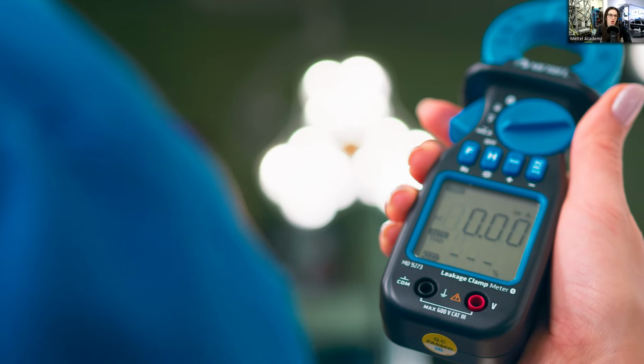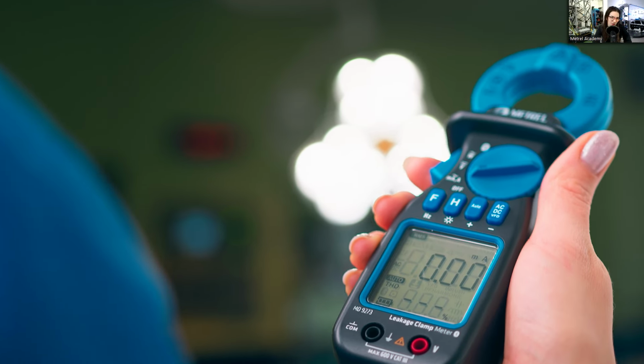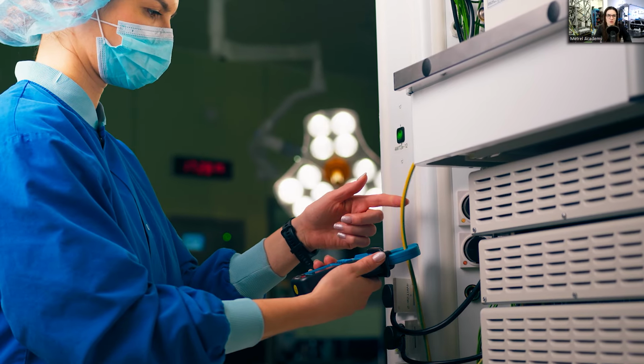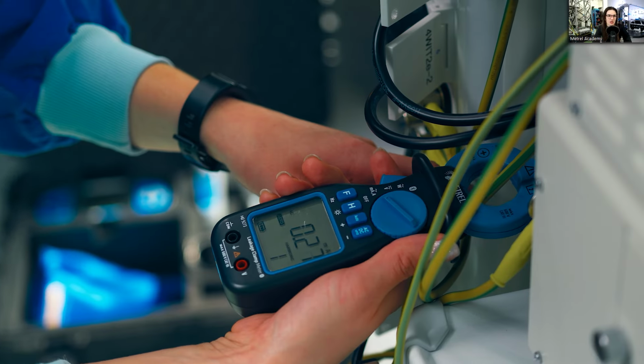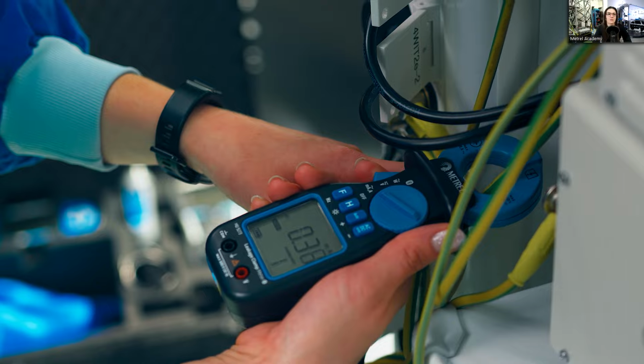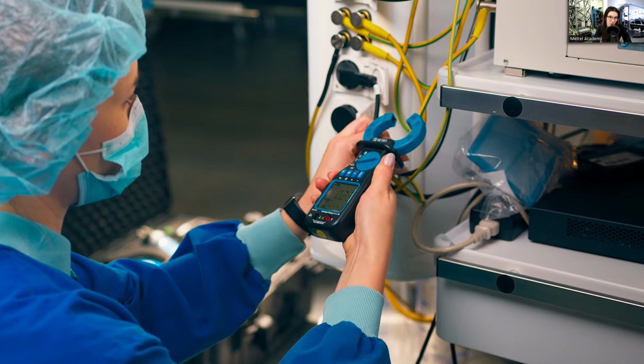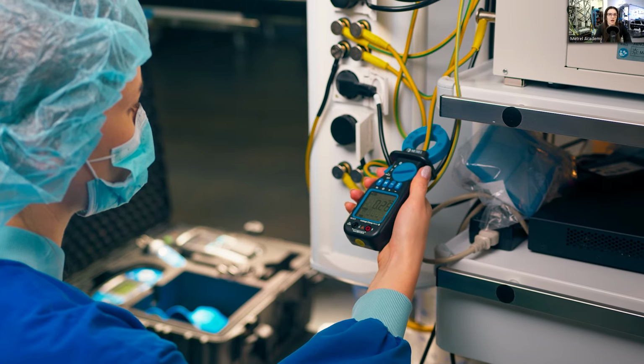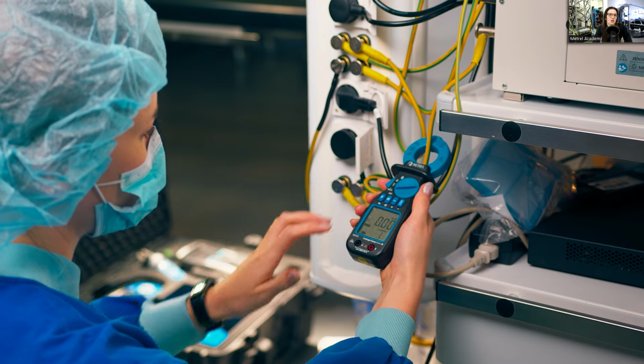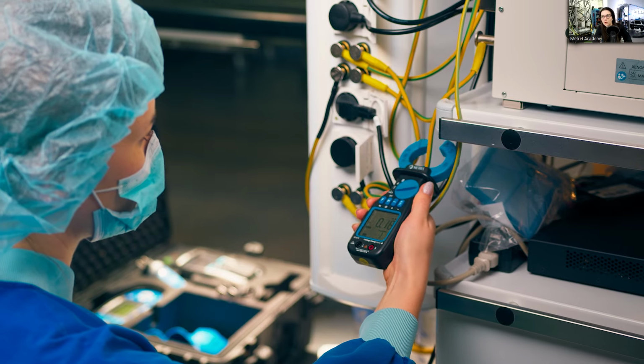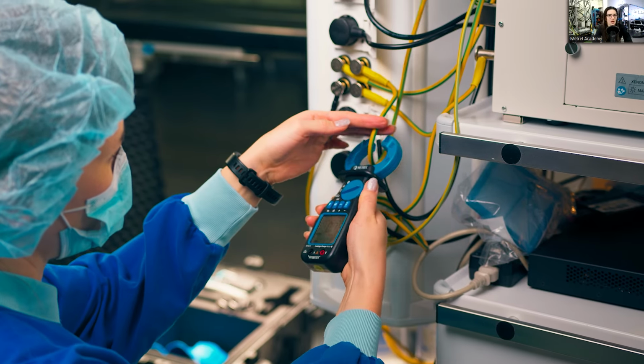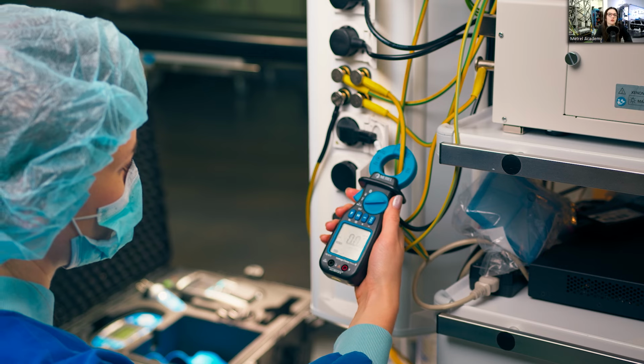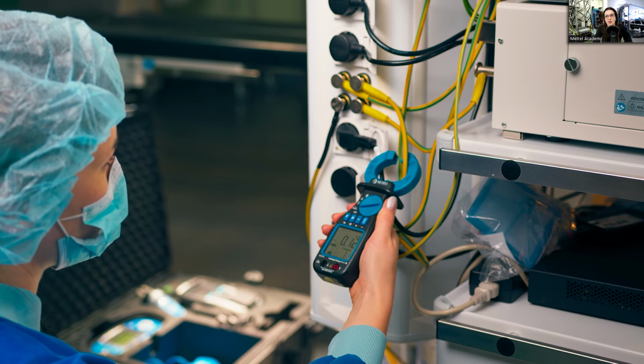The video is shot in one of the Slovenian hospitals. The surgery room is equipped with multiple devices which are stacked into a tower, and all of them have external PE wires. In the background, we can see the installation monitoring device at one point. I will point it out. And the monitoring device has started the alarm.